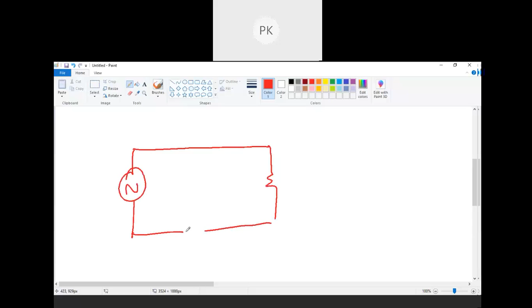Now if this is a single core cable, this armor will have a potential, and because of that potential, when the armor is earthed, what happens? You have circulating current through it in a single core cable.